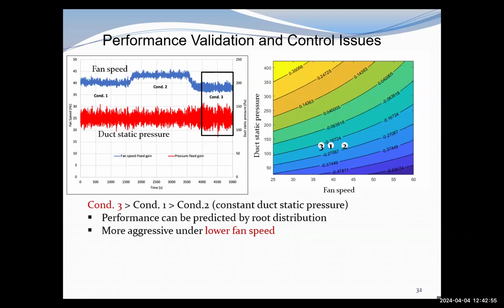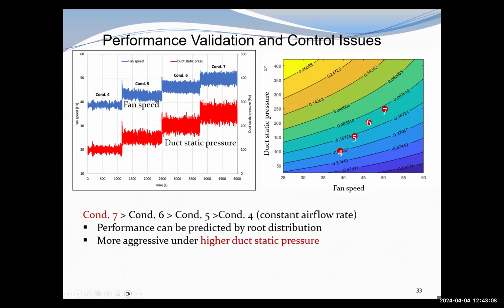So we can see that the performance can be predicted by this root distribution, and also the system will have a more aggressive response on the lower fan speed. And similarly, for conditions 4 to condition 7, we can see the cross from this one. Under condition 7, the system has the smallest negative real part, and it shows the most aggressive response. So here we can also see that the more aggressive response will happen under higher duct static pressure.